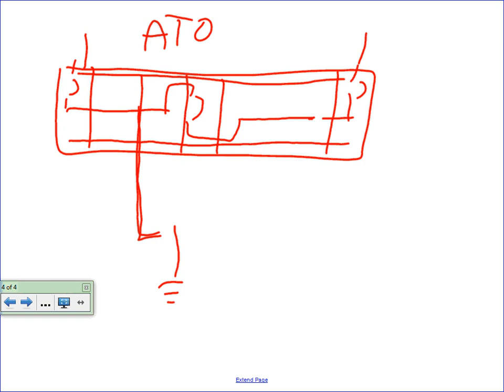What happens is we've got 2,200 amps of neutral current still flowing, but we're tied to both services because we're not breaking that neutral. So now you've got 2,200 amps of current flowing. If it's an identical system, the impedances are identical, everything, you'll have 1,100 amps flowing to this main, and 1,100 amps flowing back to this main. Okay.